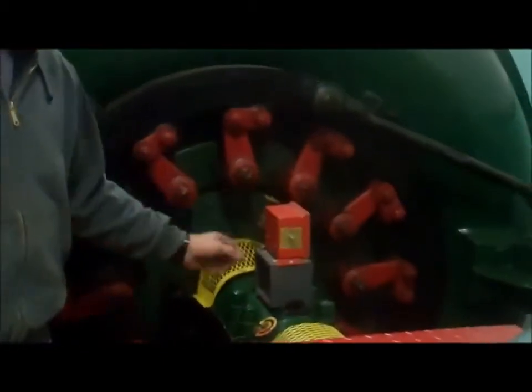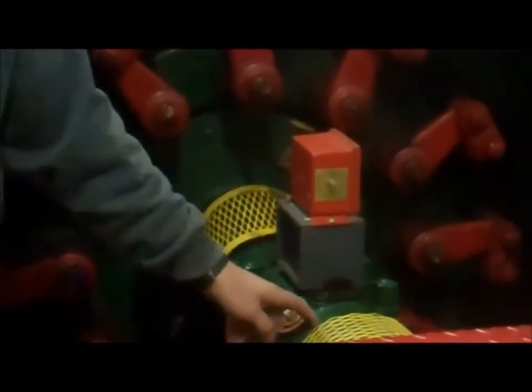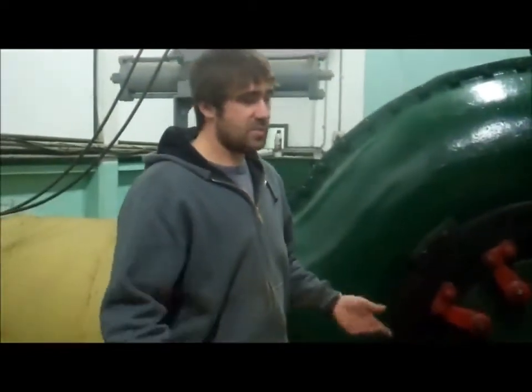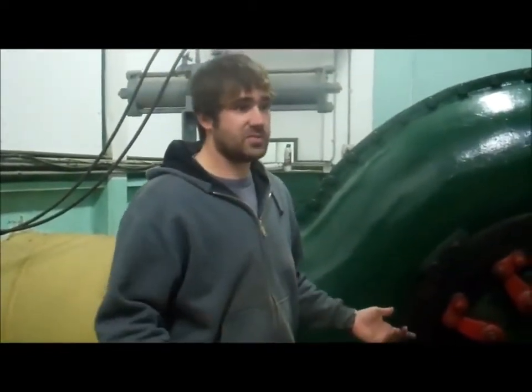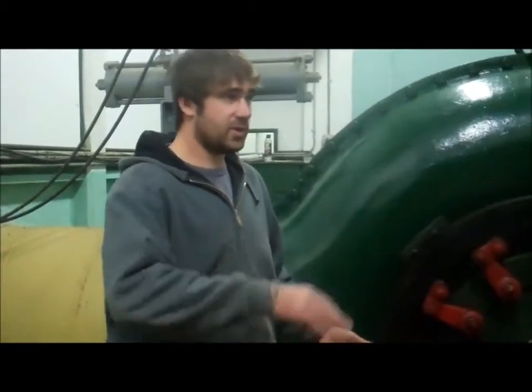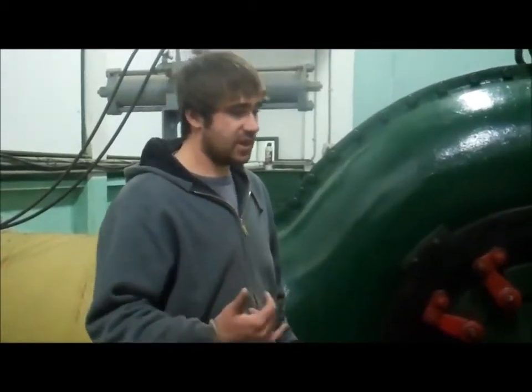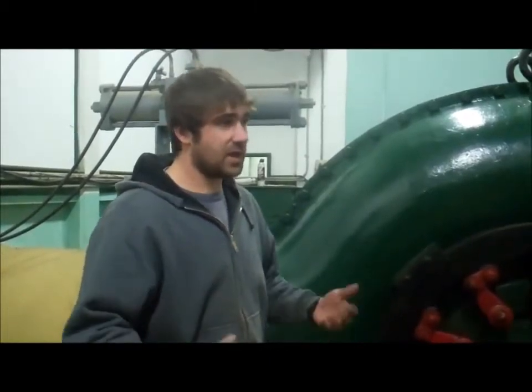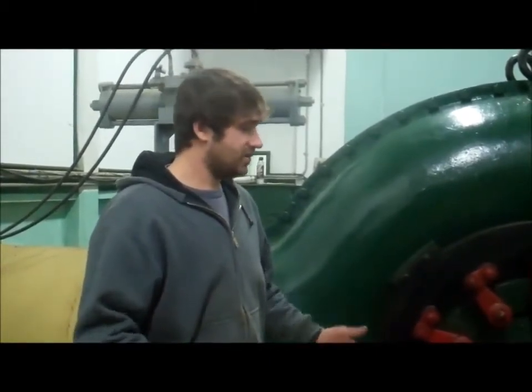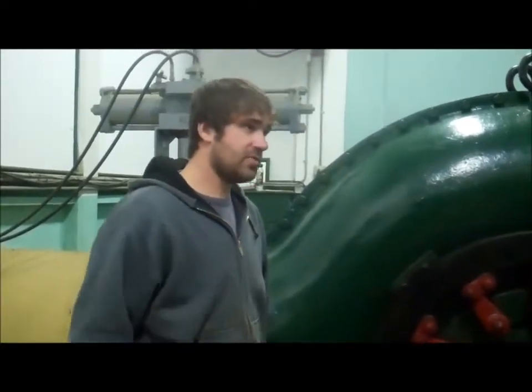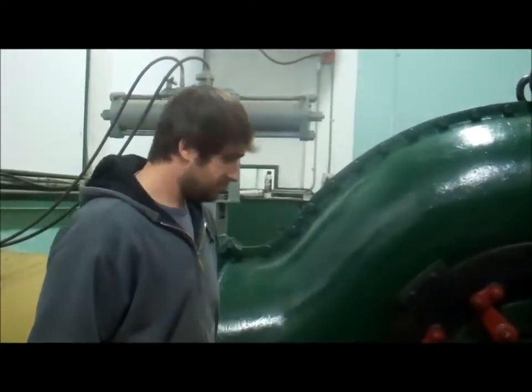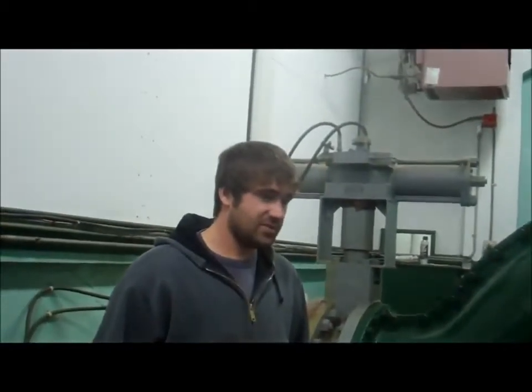And we've also got shaft protector things that detect any abnormal vibration, and we've got temperature probes on each one of them. So the computer monitors all our temperatures, all our vibrations at all times. If there's anything that goes out of the norm in their preset settings, it'll set off an alarm. It'll call my phone. And then if I don't get here in time and it keeps getting worse, or it's getting hotter, or something's going on, the computer will take over and start shutting down machines. So it's a pretty good system.